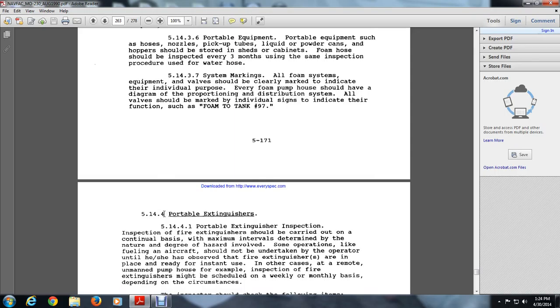5.14.4.1, portable extinguisher inspection. Inspection of the fire extinguisher should be carried out on a continual basis. Maximum intervals determine the nature and degree of hazards involved. Some operations, such as fueling aircraft, should not be undertaken until an inspected fire extinguisher is in place and ready for instant use. In other cases, with remote unmanned pump houses, for example, inspection of the fire extinguisher may be scheduled on a weekly and monthly basis depending on the circumstances.